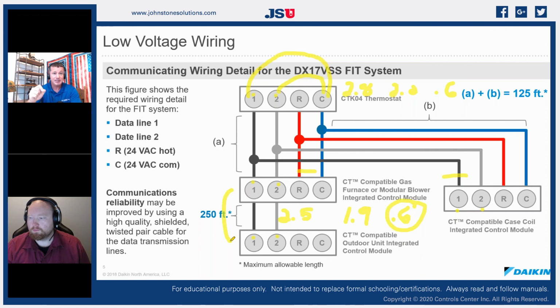But to be able to test those, we are simply going to use our meter on DC voltage, and we're just going to check between 1 and 2, and then we're going to check between common and 1 and common and 2.